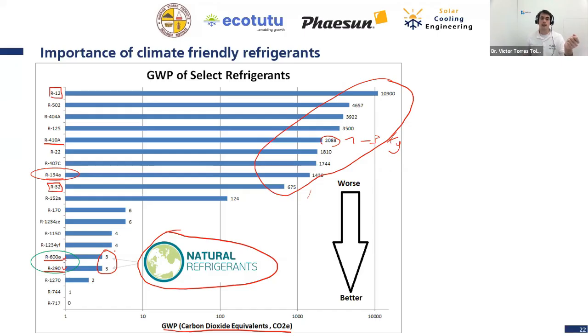The problem of those refrigerants is they are explosive, but I tell you in advance, this is not a problem in medium scale systems. It might be a problem in higher scale systems, but for air conditioning, cold rooms, and so on, this is not an issue because the amount of refrigerant inside the system is not big enough to have an explosive mixture inside the cold room or inside the house. So no problem with this. We also have lower quantities of refrigerant than the other ones. So no problem, but please be aware of the global warming potential of refrigerants.